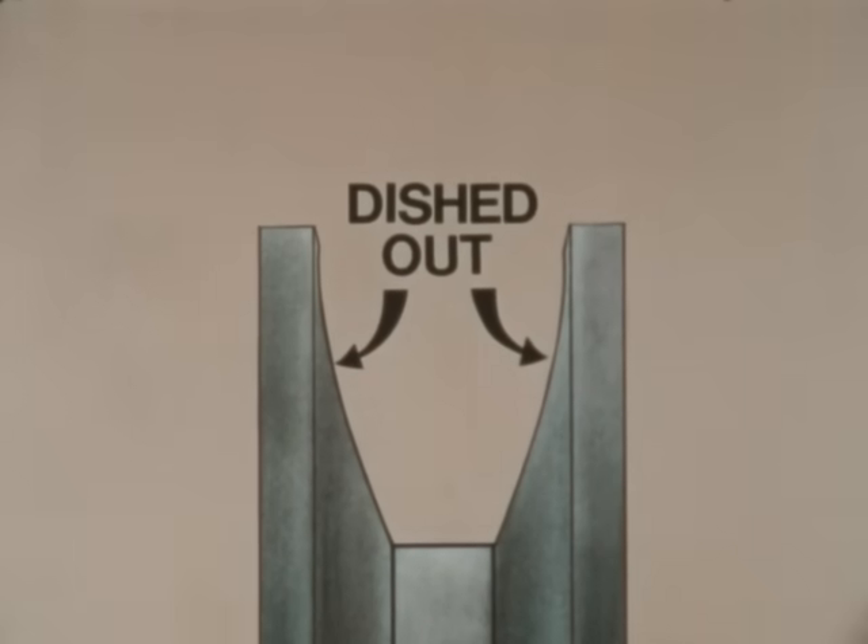A common pattern for groove wear is one where the side walls become concave or dished out. If it is to the point where the belts no longer possess their wedging action, or more than 1/32nd of an inch, then the sheaves should be replaced. Normally this will occur on the smaller shiv. If the sheaves are in good condition, then proceed to install the new belts.